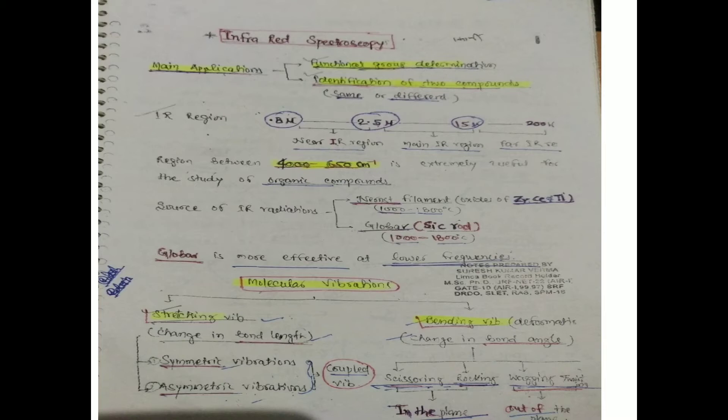The sources of IR radiation: first is the Nernst filament, which consists of oxides of zirconium and titanium, operated at 1000 to 1800 degrees centigrade. The second source is the Globar, which is a silicon carbide rod. The Globar is more effective at lower frequencies.